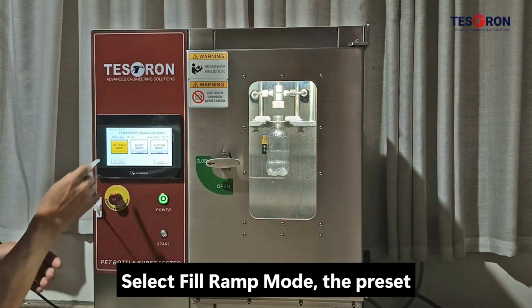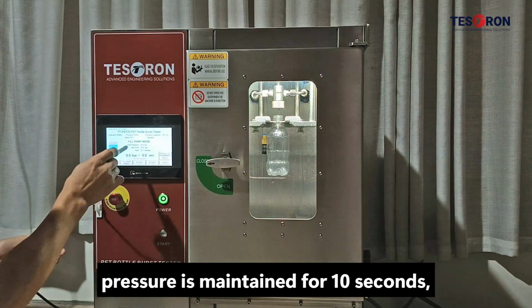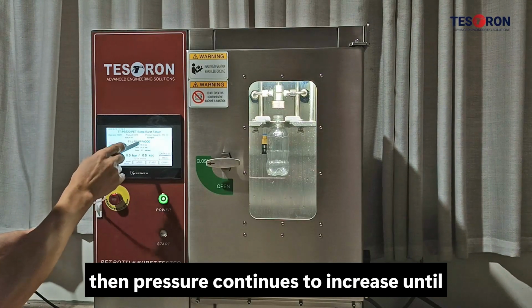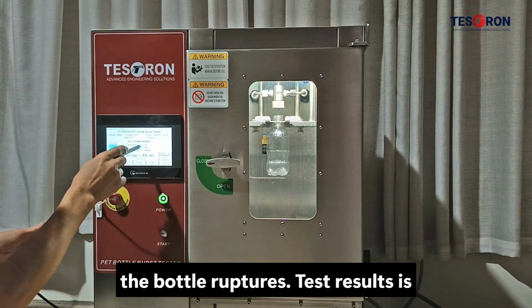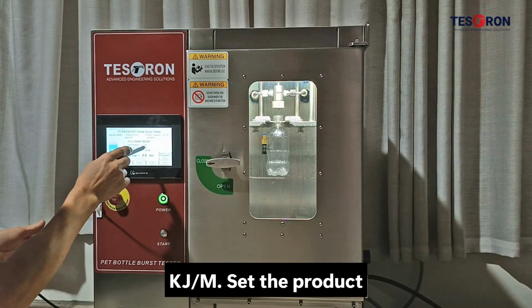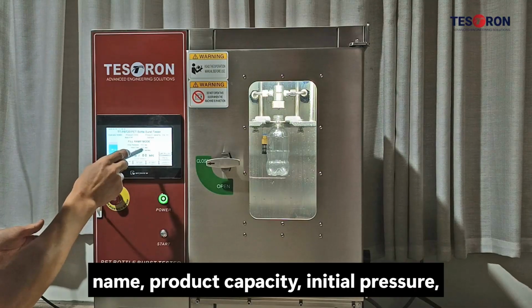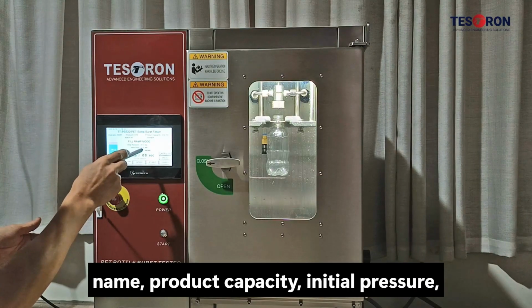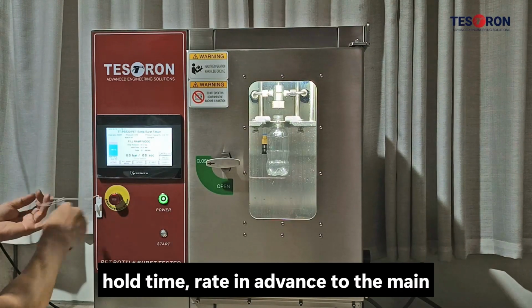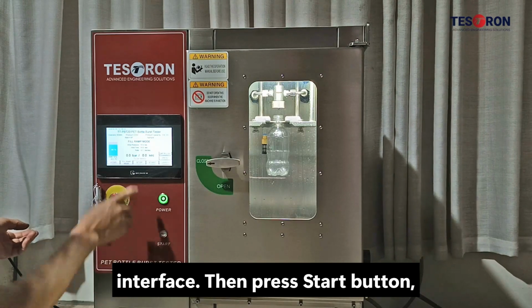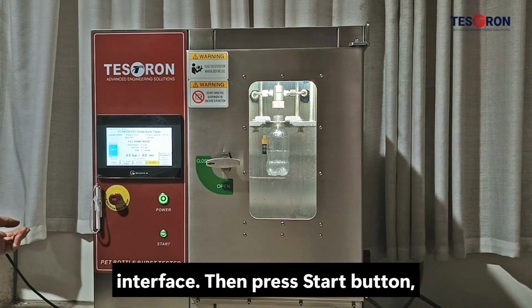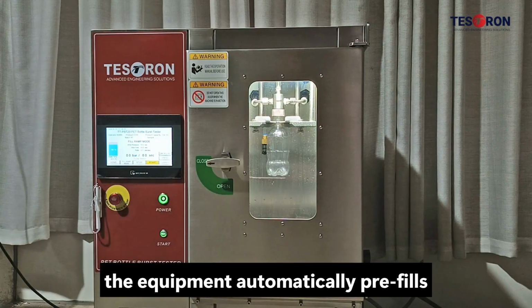Select Fill Ramp Mode. The preset pressure is maintained for 10 seconds, then pressure continues to increase until the bottle ruptures. Test results is kJ/M. Set the product name, product capacity, initial pressure, hold time, rate in advance to the main interface. Then press Start button. The equipment automatically pre-fills water.